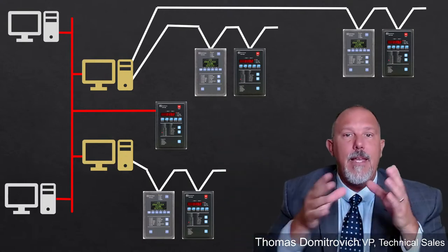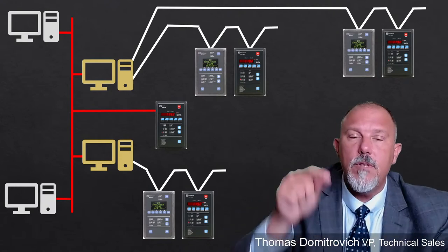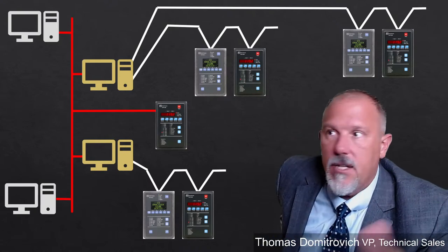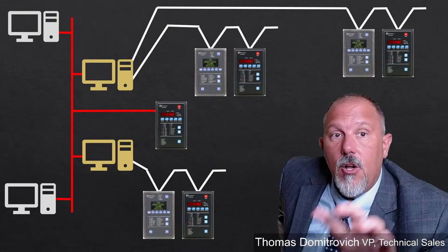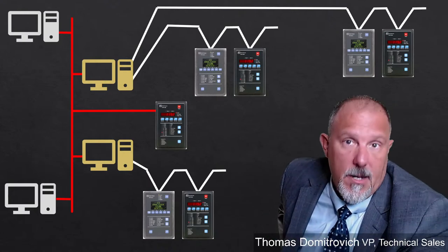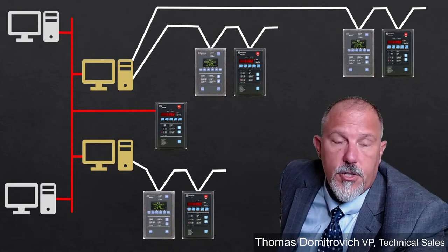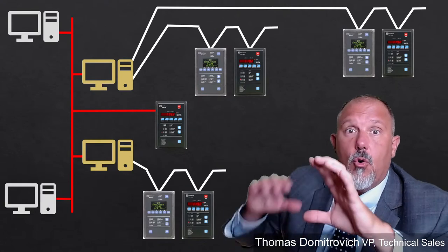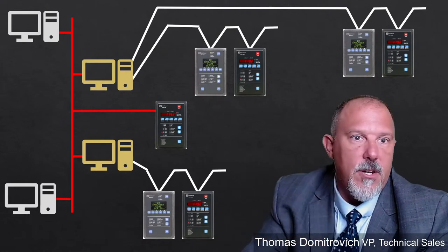Do I need to put a computer in between these meters? And what's the role of that computer? If I need local data logging, say for example, I don't want to rely on my Ethernet LAN because it keeps going down, I can create smaller local area networks. And I can consider both of these a little local area network, but via Modbus RTU, say, or INCOM or whatever proprietary protocol or open protocols.